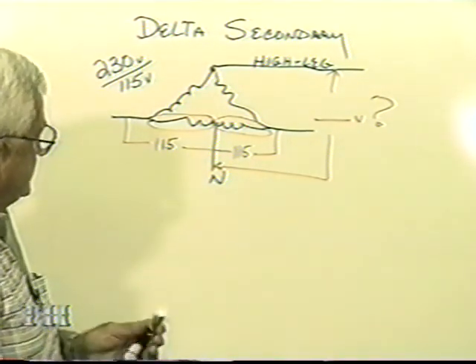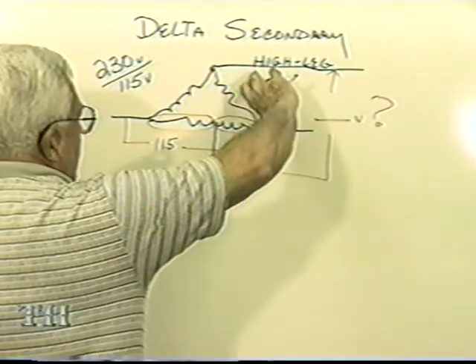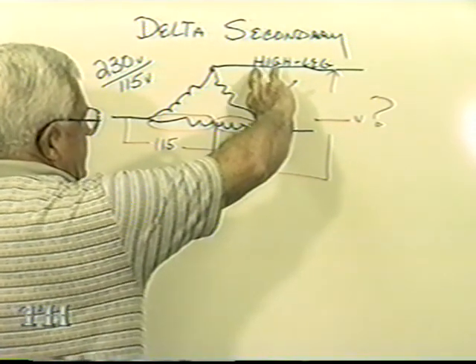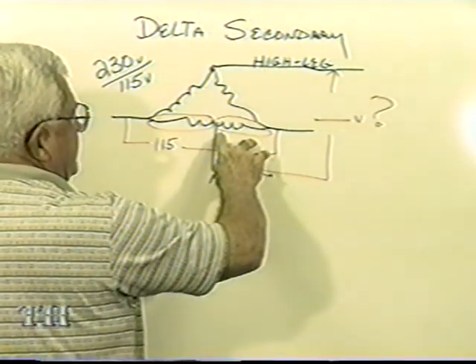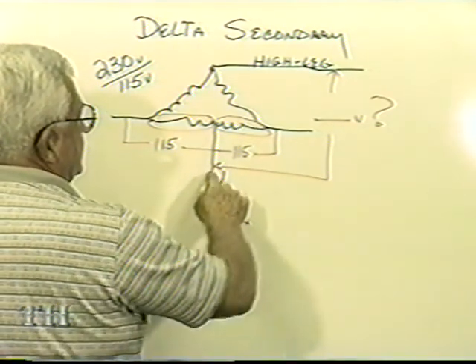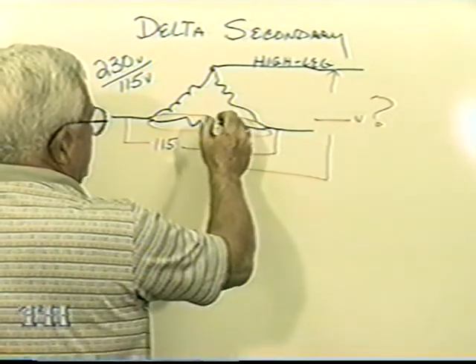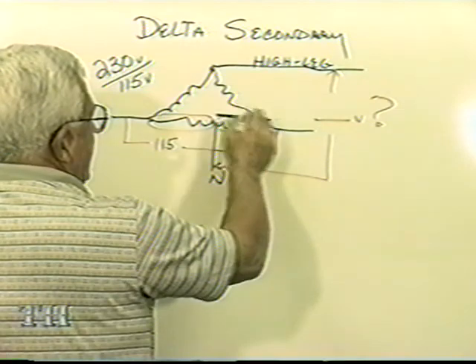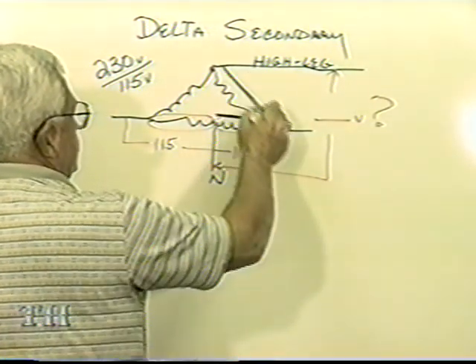Well, the picture you want to see is you're no longer reading one phase, and you're no longer reading half a phase. From this point, neutral, to this high leg, look what you're doing. You're actually coming across a half a winding and a full winding.